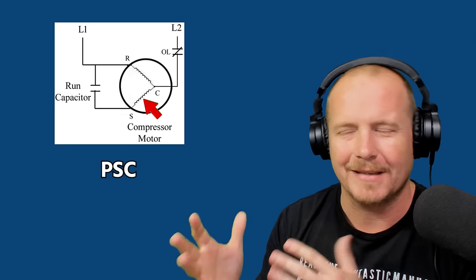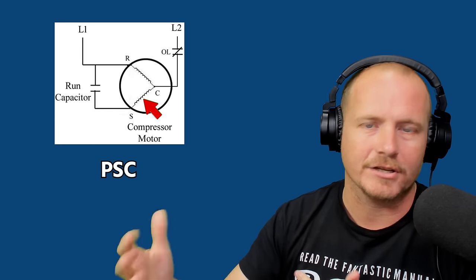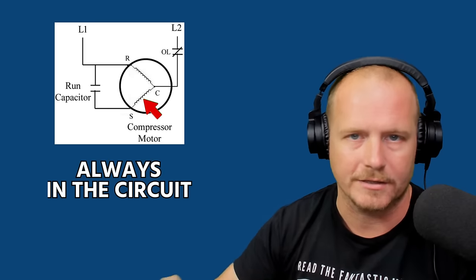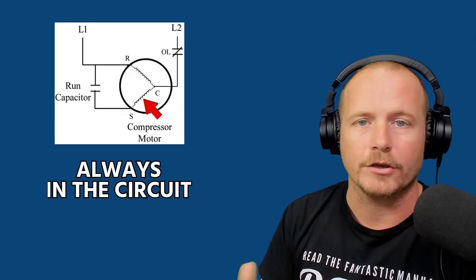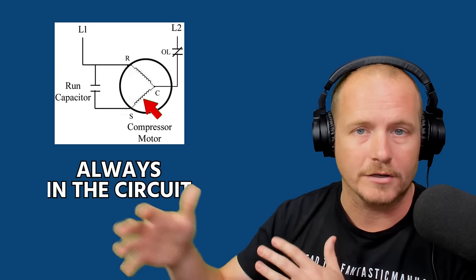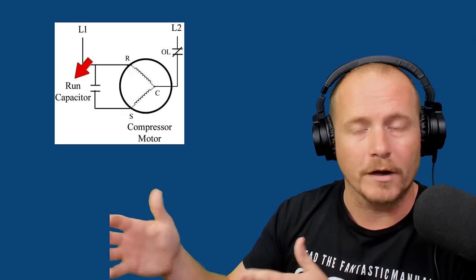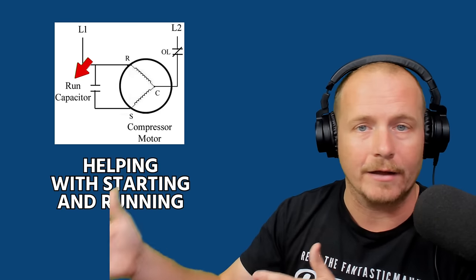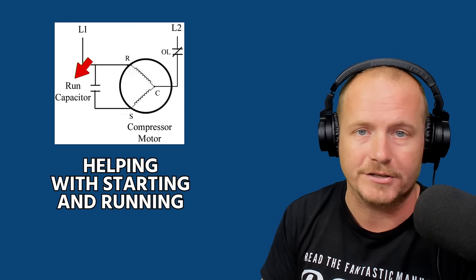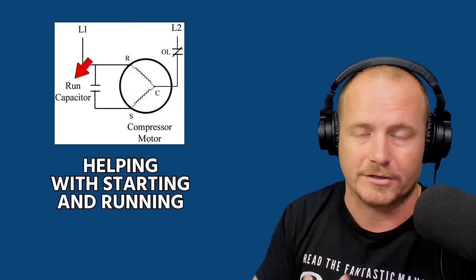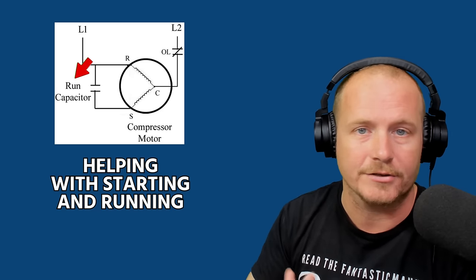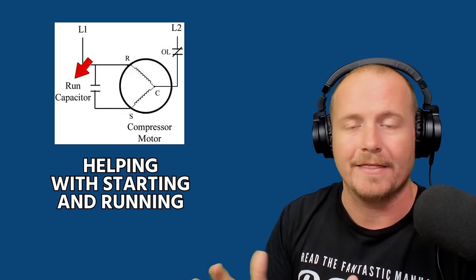But on a PSC, it's kind of a misnomer because it's not just in while it's starting, it's always in the circuit. And especially if we're not using a start capacitor or a hard start kit, your run capacitor is helping with starting and running, and there's really nothing else going on there. It's operating in the same way when it starts and when it runs. There's no relays, there's nothing taking it out of the circuit. It's just in there all the time.